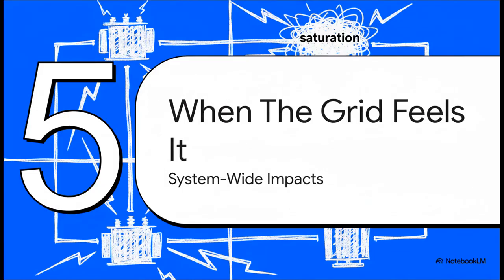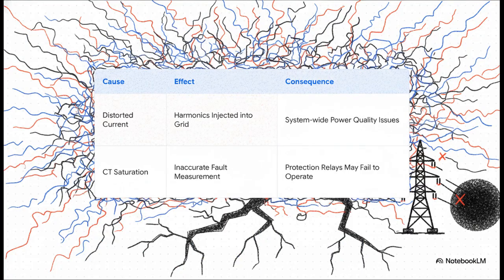A problem in one transformer is bad enough, but these things aren't islands. They are vital nodes in a massive interconnected grid. And when a big transformer saturates, you better believe the entire system is going to feel it. This is where the consequences really start to scale. Those nasty current harmonics we mentioned, they don't just stay put. They get injected back into the grid, basically polluting the power quality for everyone connected to it.